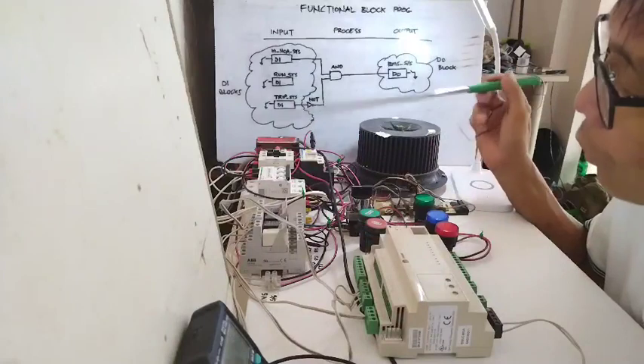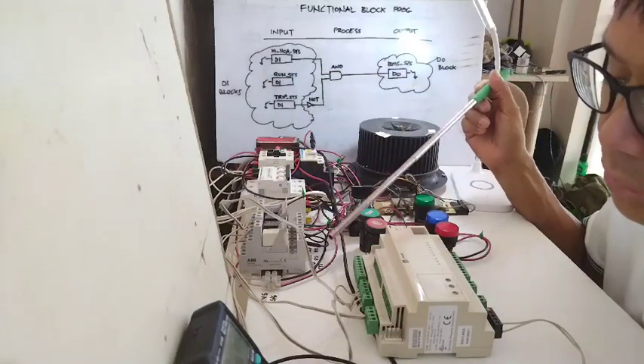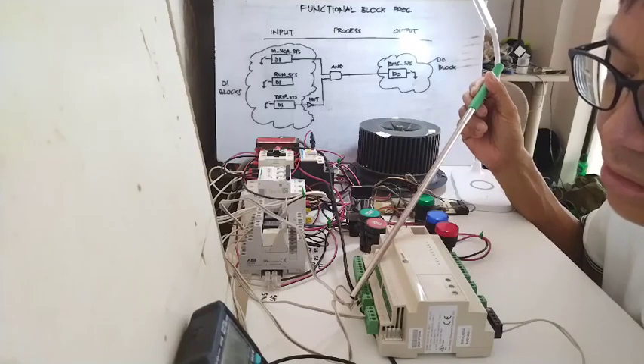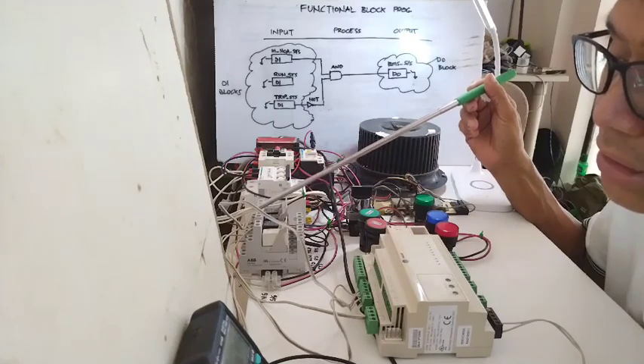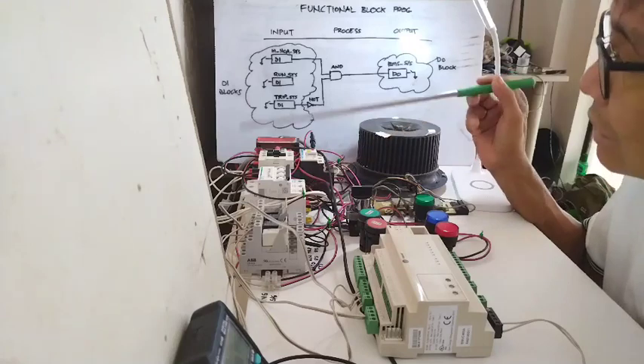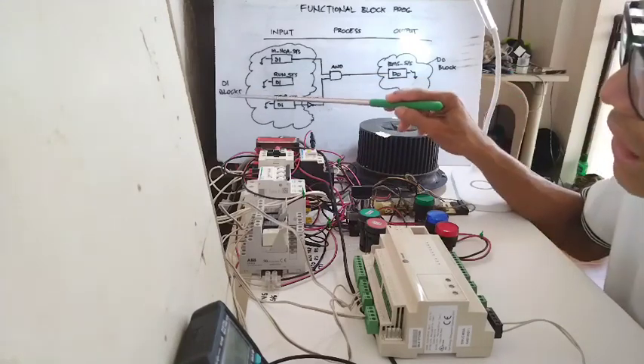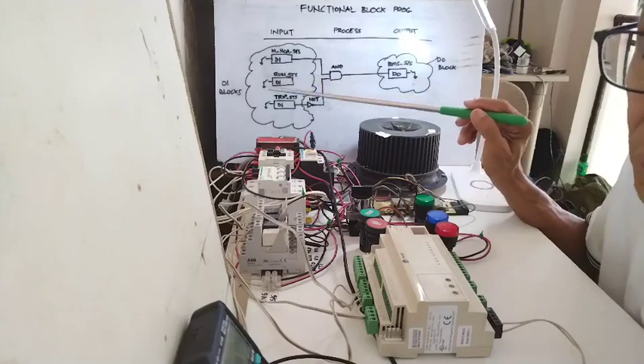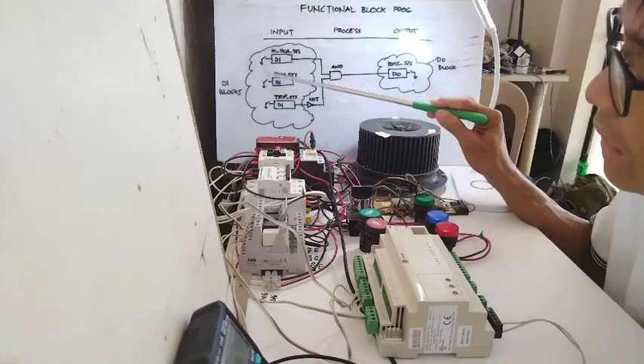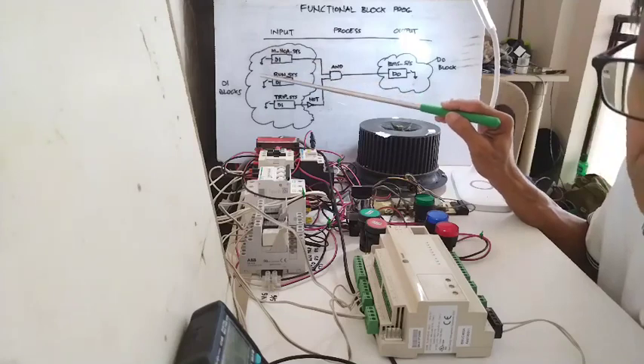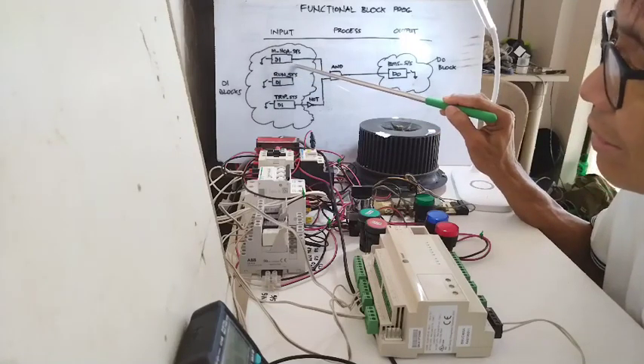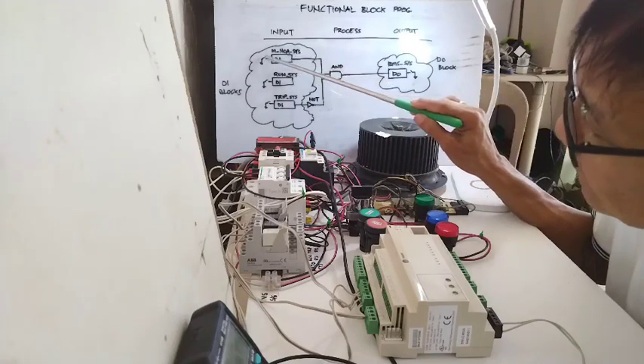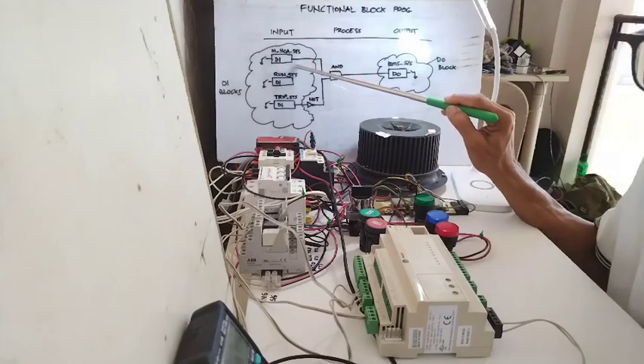When I say map, it means where this DI block will take the information from — it will take it from the controller BI 1, and BI 1 gets the information from the control panel providing the hand-off-auto status. The DI block will receive a normally open or normally closed contact; it is a volt-free contact. We can give just an open or closed contact here. When it is closed, this output will become 1.